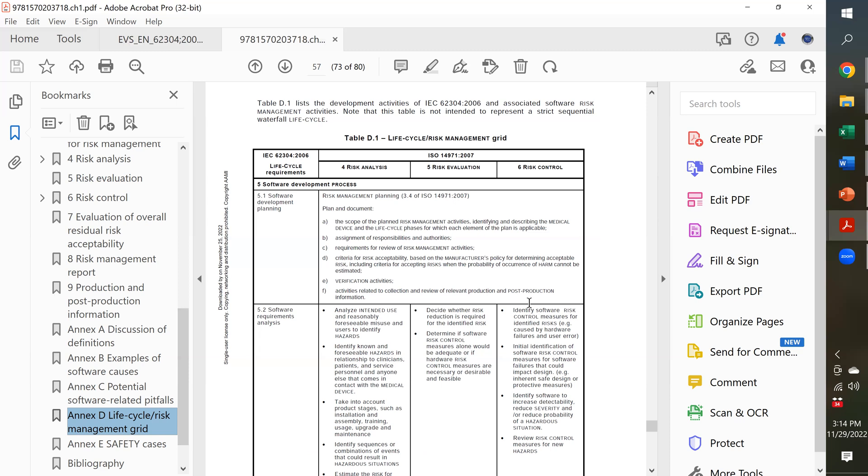There's a traceability matrix that's required for submission. That's part of your software validation documentation. So, if you don't have all the hazards identified, then in the early part of the development, you might not have included a risk control in the design of the software. So, now you're stuck doing a tap dance to try to explain why you don't need it when you probably do.